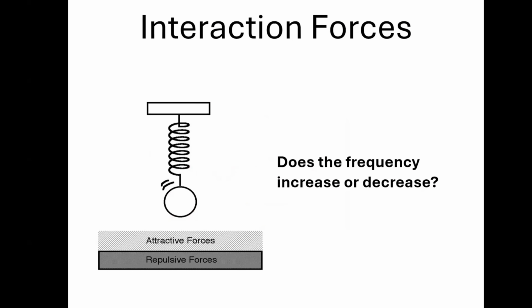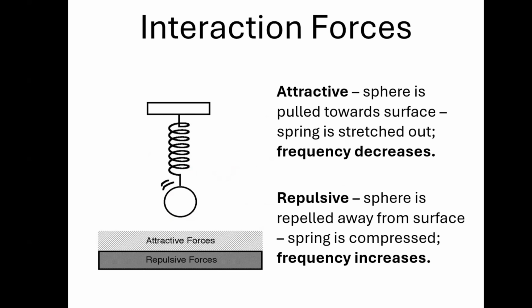For amplitude modulation mode, we need to consider the interaction forces. In contact mode, we are operating entirely in the repulsive regime. An easy way to do this is to think of our lever as a spring. As the tip gets close to the surface, the resonance of this lever spring will change. The long-range attractive forces will act to pull the tip to the surface, the spring will elongate, and the resonance frequency will decrease. As we get closer, the short-range repulsive forces will push the tip away from the surface, compressing the spring, and the resonance frequency will increase.